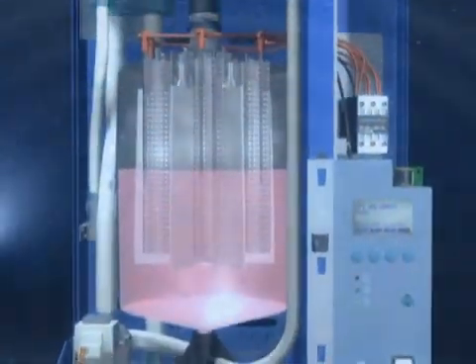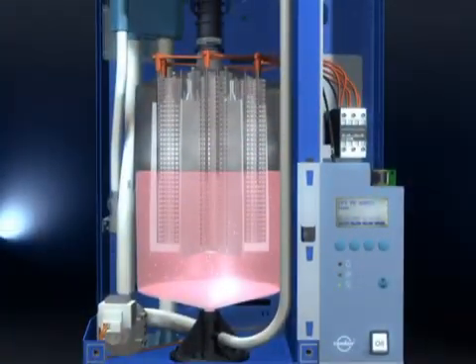The minerals set free during evaporation steadily increase the conductivity of the water. As the conductivity progresses, steam production rises too. To ensure the required steam output at any time, the proportion of salts and minerals must be reduced.